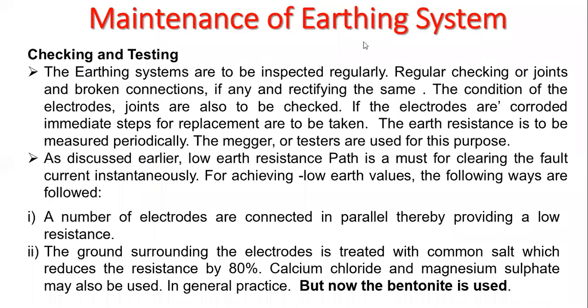So next is maintenance of earthing system. In this, first one, checking and testing of earthing system. So first of all, the earthing system is to be inspected regularly. The regular checking of joints and broken connections. That means you have to regularly check the joints, whether they are broken or not. If any fault or damage is there, then it can be rectified. Then the condition of the electrode and joints are also to be checked. Regularly you have to check the condition of that electrode, whether it is corroded or not, whether the joint is loose or not. That means you have to continuously check. If the electrode is corroded, then immediate steps for replacement are to be taken. That means if corrosion is there, we have to replace that electrode.